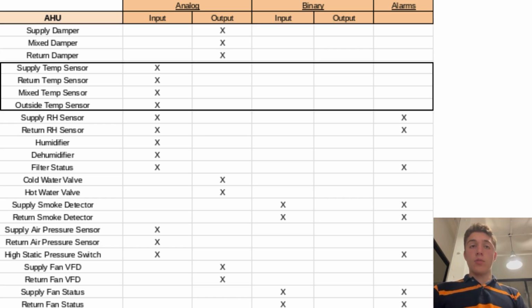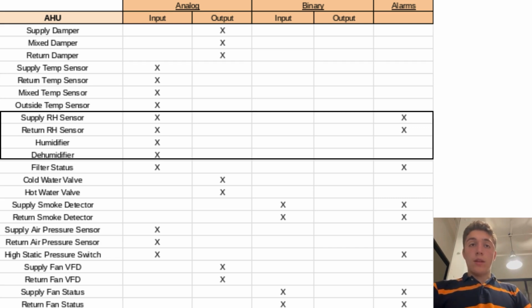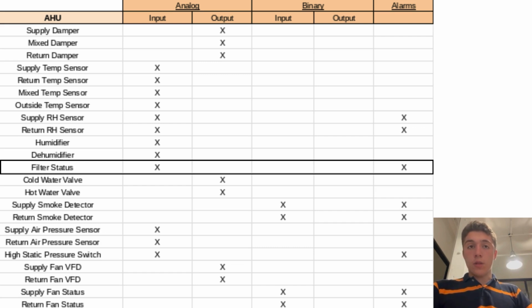Then we have a bunch of temperature sensors, the supply, return, mixed, outside temperature sensor. These are all analog inputs. Then we have the supply humidity sensor and the return humidity sensor. These are also inputs because they measure the amount of relative humidity. Next, we have a humidifier and dehumidifier, which are controlled by analog inputs. Then we have a filter status, which is an analog input, but that's routed to an alarm, just to let us know if this filter needs to be changed.